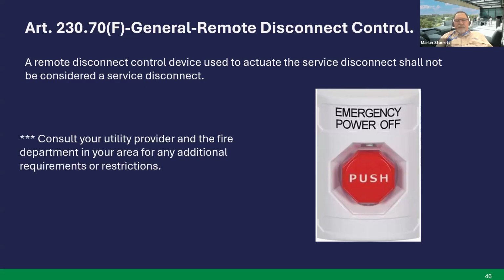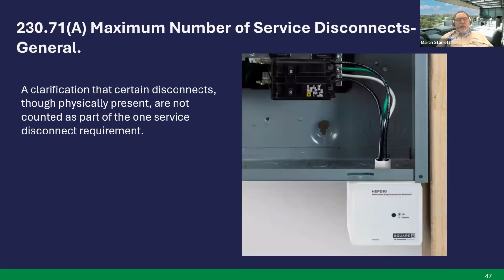Make sure with these buttons that you consult your utility provider and the fire department in your area for additional requirements or restrictions. Next slide. 230.71(A), maximum number of service disconnects, general. A clarification that certain disconnects, though physically present, are not counted as part of the one service disconnect requirement, such as you see here, surge protection device, power control equipment, etc.